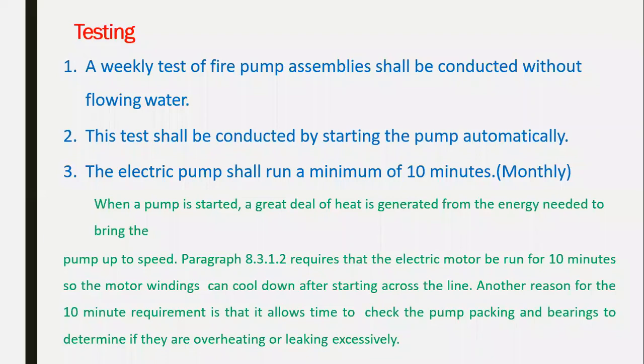This is the first stage of the testing of the inspection. Going for the testing, how many tests and what we have to do within the test. A weekly test for the fire pump should be conducted. This test shall be conducted by starting the pump automatically. For the electrical pump, it has to run for 10 minutes monthly, not required weekly. To the electrical pump, it has to run 10 minutes only monthly.